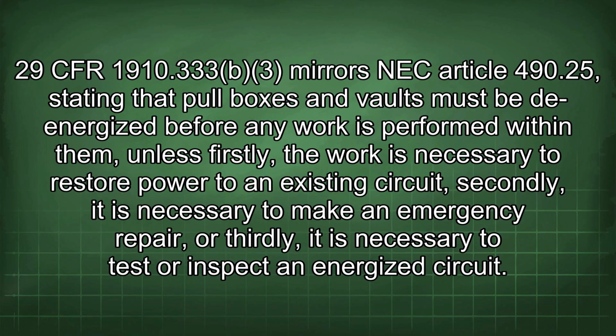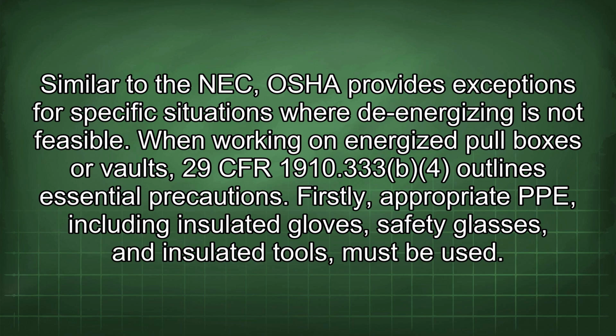29 CFR 1910.333 mirrors NEC Article 490.25, stating that pull boxes and vaults must be de-energized before any work is performed within them, unless, firstly, the work is necessary to restore power to an existing circuit, secondly, it is necessary to make an emergency repair, or thirdly, it is necessary to test or inspect an energized circuit. Similar to the NEC, OSHA provides exceptions for specific situations where de-energizing is not feasible.